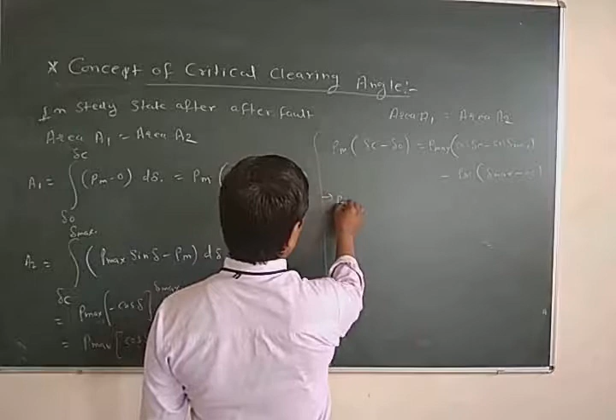Now we can solve these equations. It becomes Pm delta C minus Pm delta 0 equal to P max cos delta C minus P max cos delta maximum plus Pm delta C minus Pm delta maximum. So there is Pm delta C on both sides, so Pm delta C cancels. Now from this, P max cos delta C is equal to Pm delta 0 minus P max cos delta maximum minus Pm delta maximum. So cos delta C is equal to (Pm delta 0 minus P max cos delta maximum minus Pm delta maximum) divided by P max.